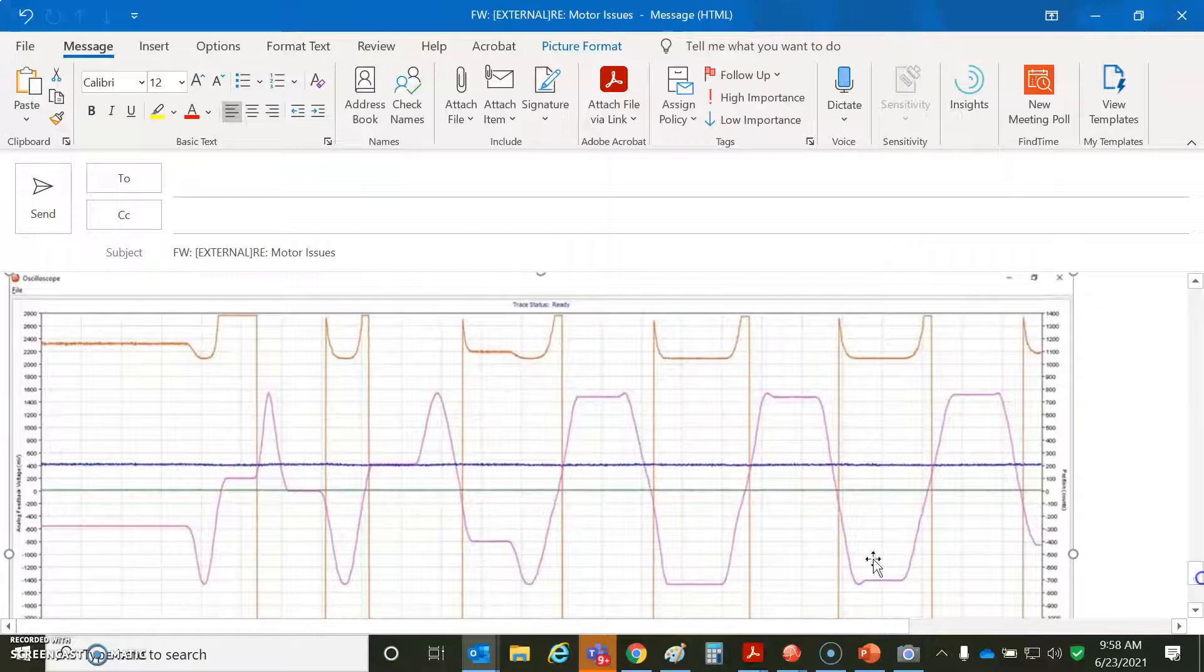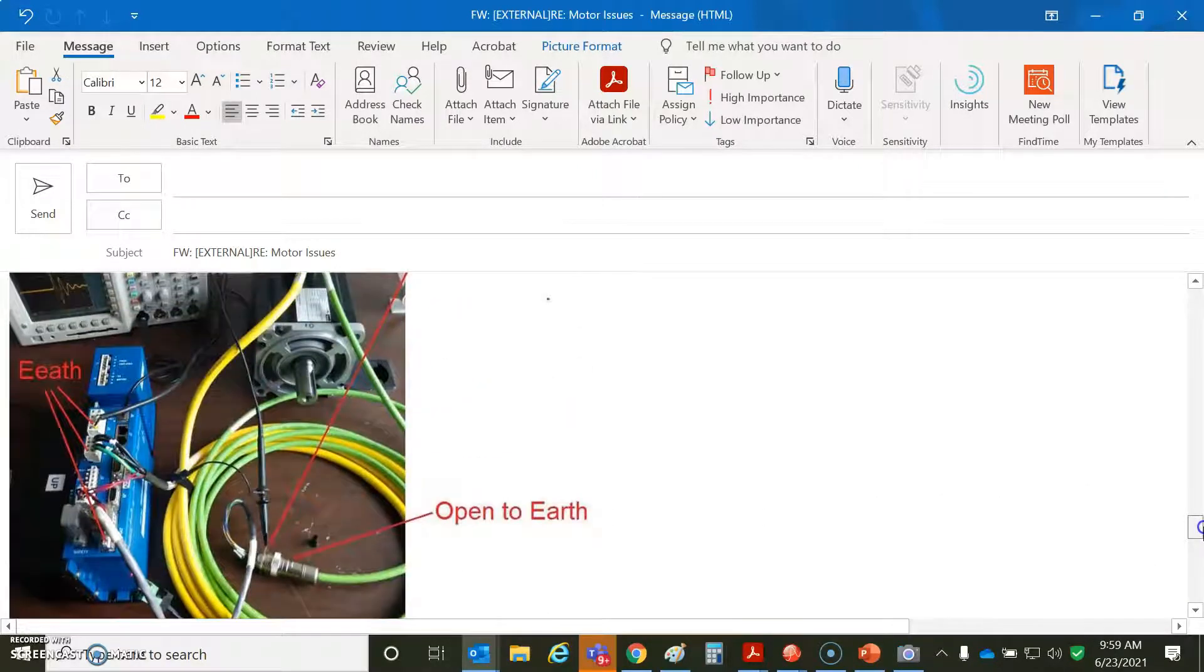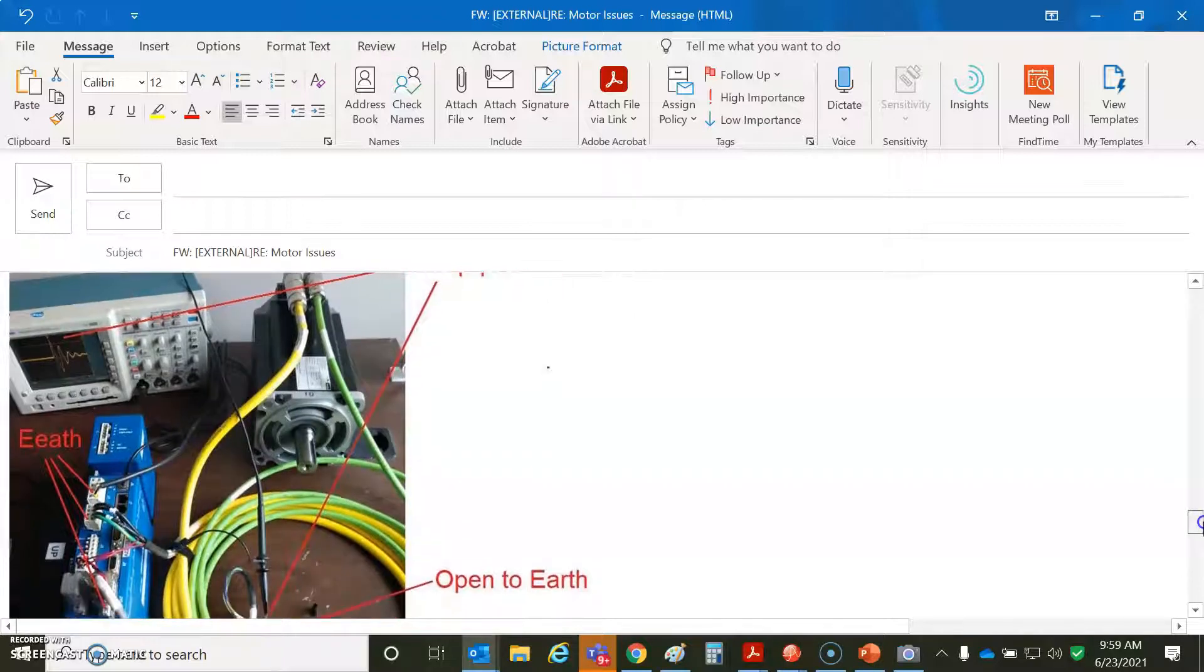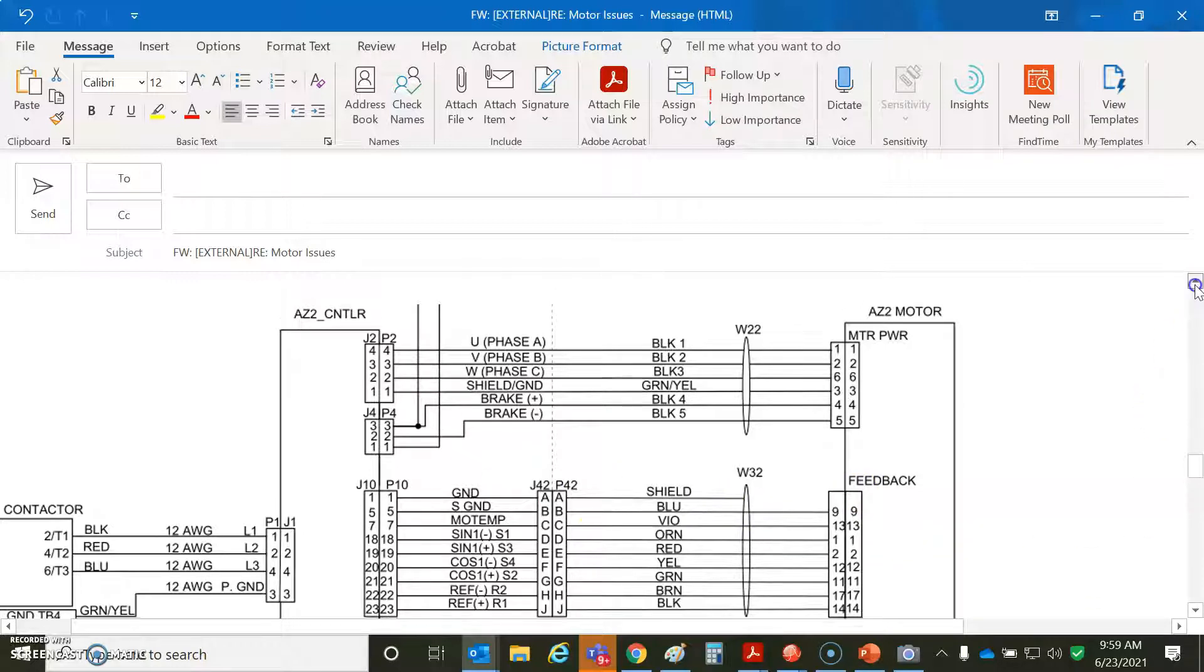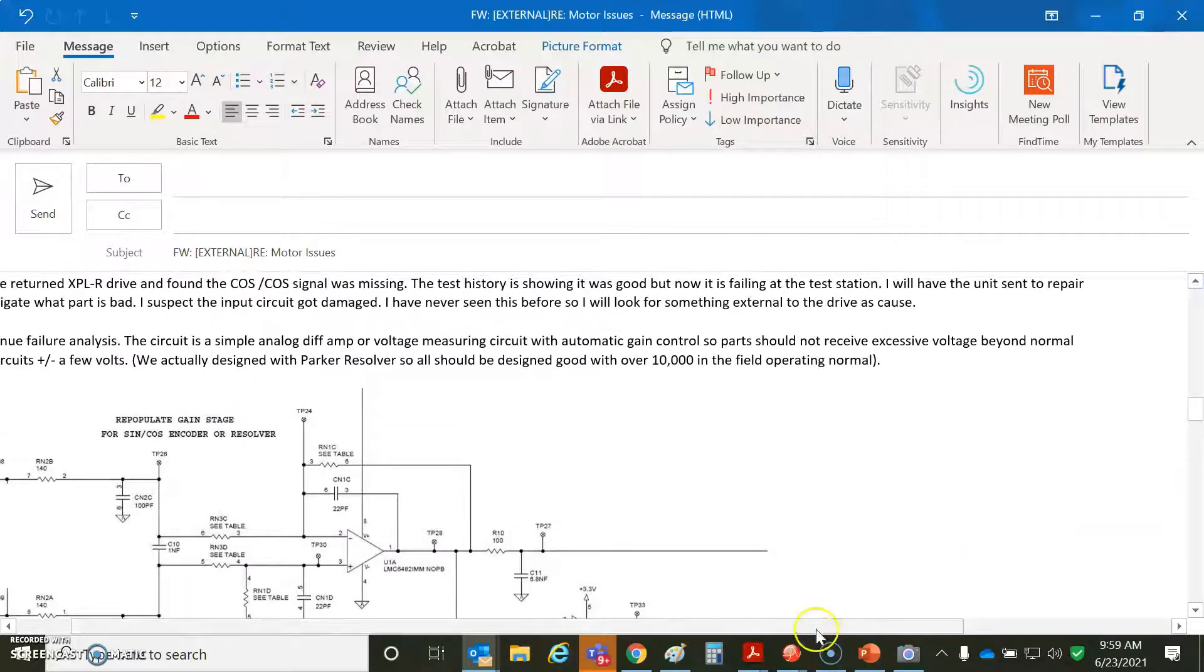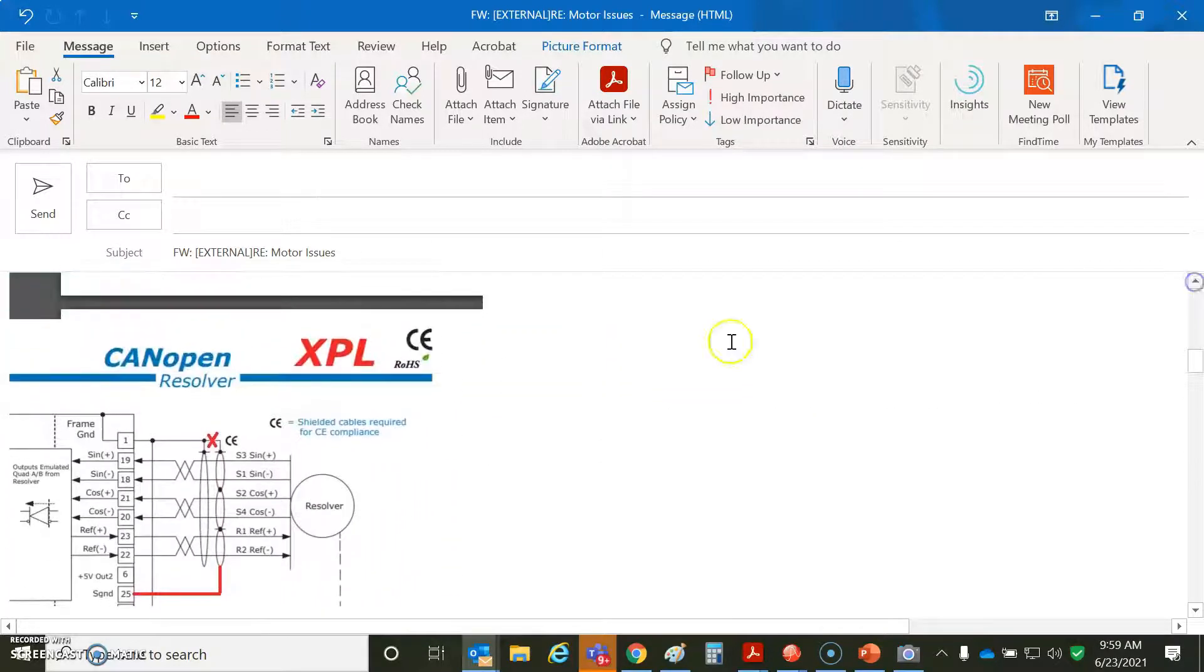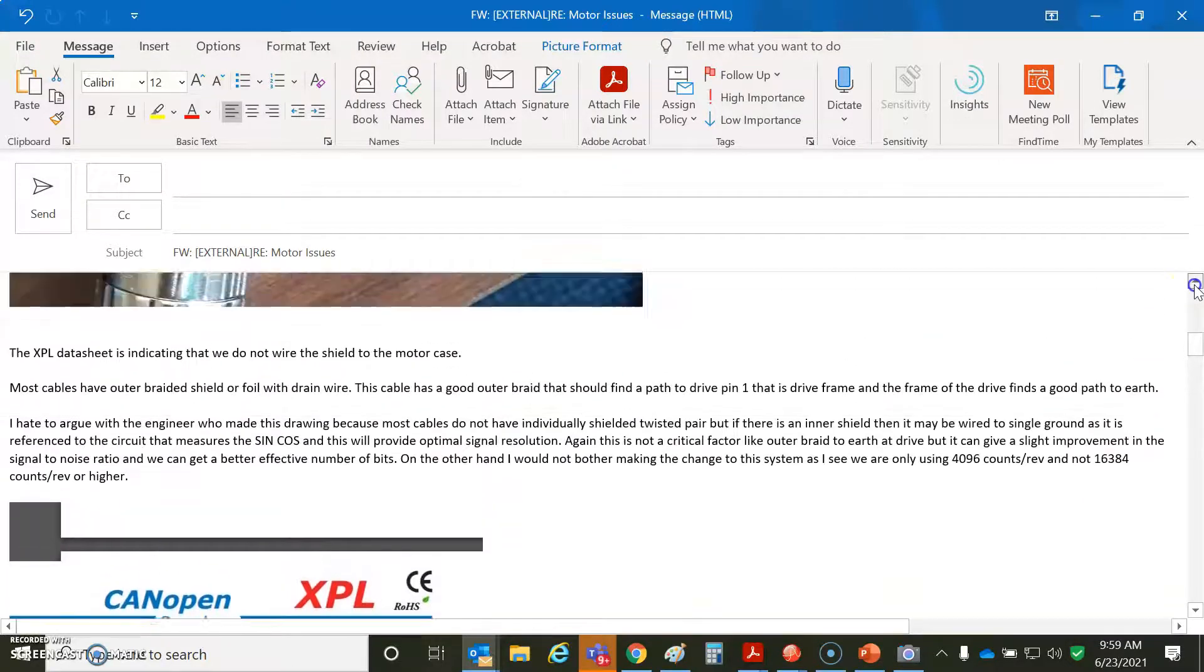Okay, so we'll take a look at, this is a good sine, but it's a bad cosine. And so the customer was having a problem with the drive. We get it set up here and we see 60 volts peak to peak noise. And we wonder why the resolver circuit's blown up. The diagram is clearly showing the feedback shield not connected to the motor case. But, yeah, here's the resolver circuit just differentially measuring a voltage. So nothing fancy there. And, yeah, don't connect the shield to the motor case.